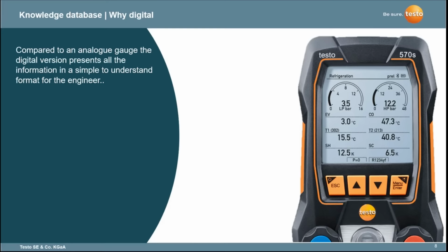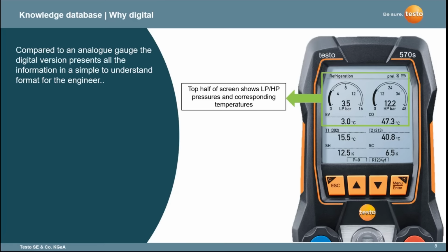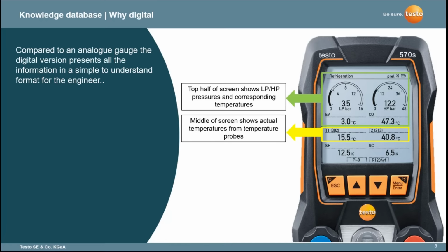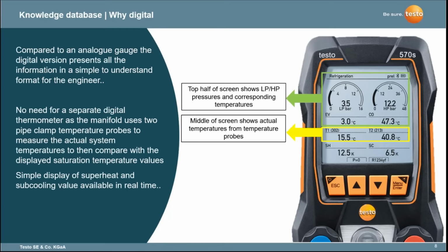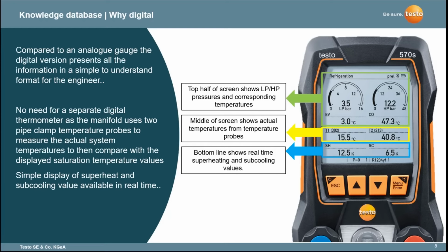And one of the key things is the way the information is displayed. Compared to an analog manifold, a digital manifold provides the information in a much simpler to understand way. At the top of the instrument, we've got very much like a traditional set of gauges. You've got the low pressure and high pressure side of the gauge with your pressures displayed and your saturation temperatures. You've then got two temperature readings typically coming in from a couple of Bluetooth pipe clamp probes, showing you your T1 and T2 temperature, so your temperature on the outlet of the evaporator and obviously the temperature on the outlet of the condenser. And then the instrument can look at those readings, compare them to the saturation, and show you in real time the superheating and subcooling values. So very, very simple to see all the information you need to know about the system on one screen. There's no jumping between screens. It's all in clear view on one single screen.